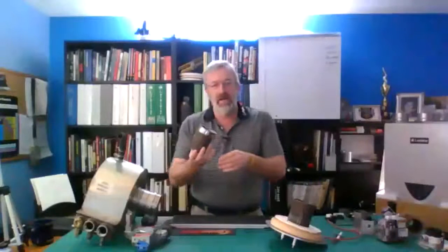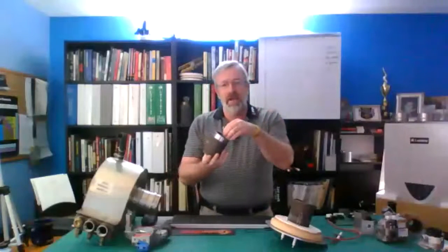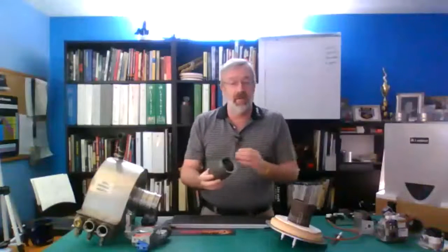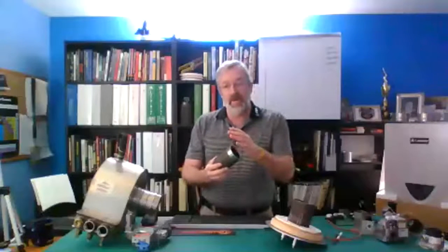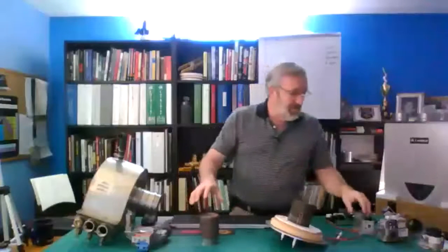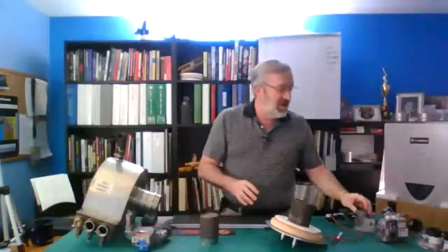A dirty burner. So if I'm pushing through here and I plug this all up, I'm reducing the ability of my fan. It's an ECM fan. If you're familiar with ECM, it's going to back up. That's all it's going to do. Now, it might be trying to go at 100% and doing its thing, but there's so much restriction on it. So if that begins to happen, my airflow drops off, my flow through my venturi changes the gas that I'm pulling.